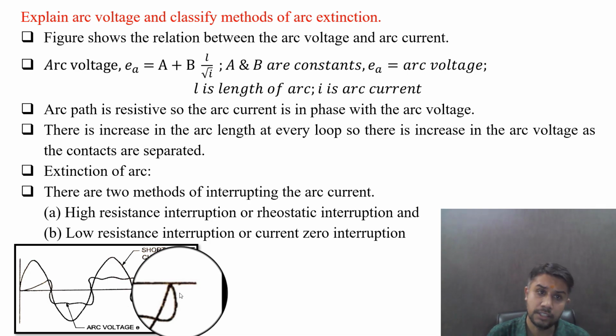The path of this arc is highly resistive, so the arc current is naturally in phase with the arc voltage due to the resistive nature. There is an increase in the arc length at every loop, so there is an increase in the arc length and arc voltage as the moving contacts are separated from the fixed one. The extinction of the arc can be done with the help of two different methods. One is the high resistance interruption or rheostatic interruption, and the second one is the low resistance interruption or current zero interruption. On the basis of the arc extinction method, we can classify them in these two ways.